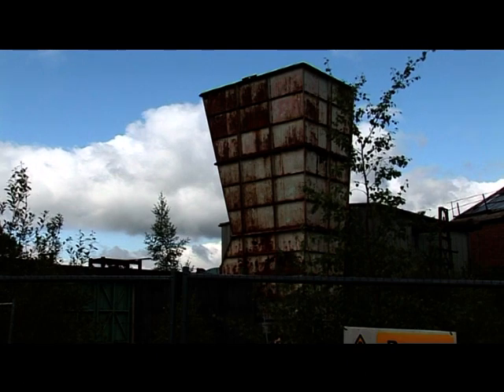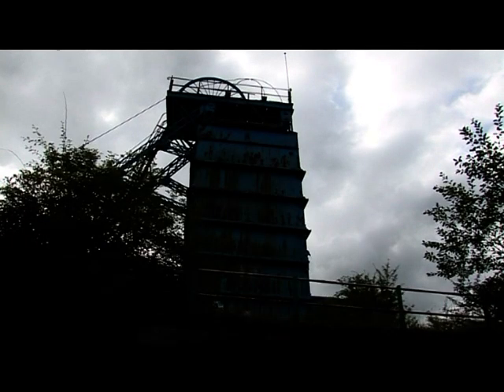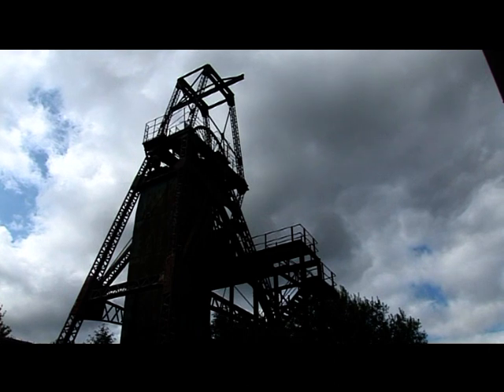I'm walking past the main colliery fan, which is on my left, which is a relatively new installation and is all electric. Originally, colliery fans were steam driven, but with the advent of electricity, it became much more efficient. The Institute and Platte shafts have iron structures from floor to the top, and they are what is known as the upcast shafts. So the fan sucks air out of the pit and goes down the Husker and Windstanley, which are open shafts, and is drawn up the Institute and the Platte. And I think this fan drew 384,000 cubic feet a minute through the workings.